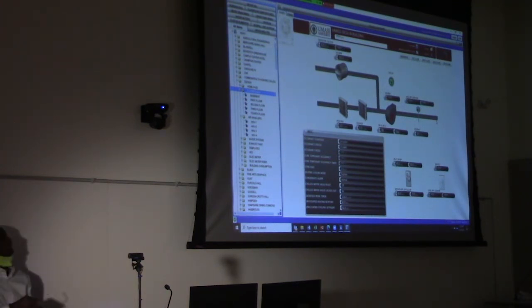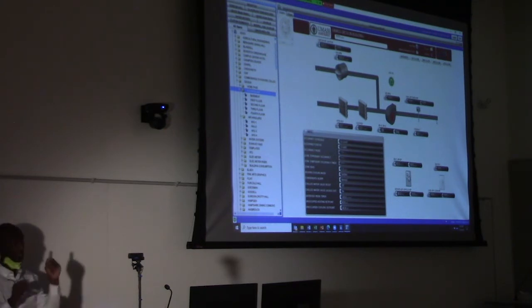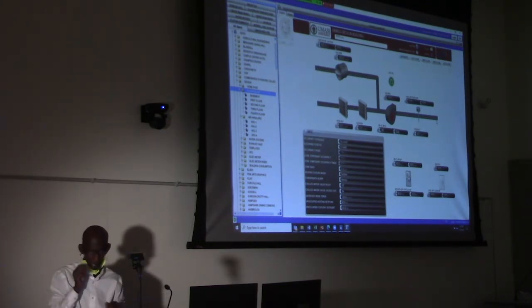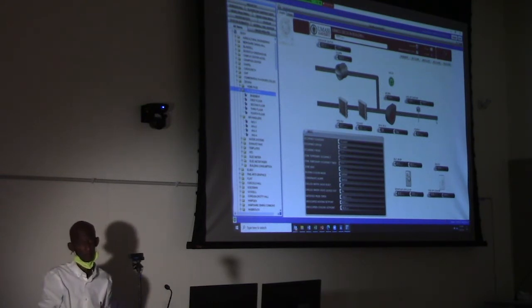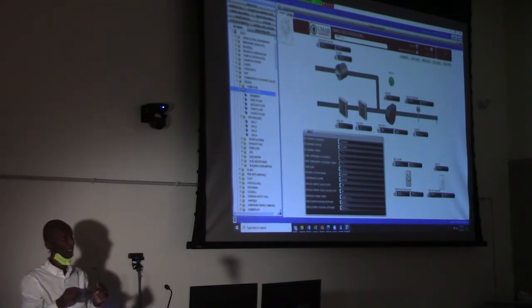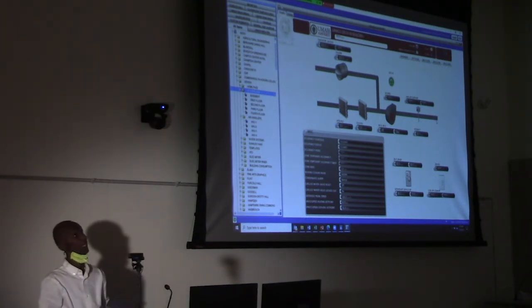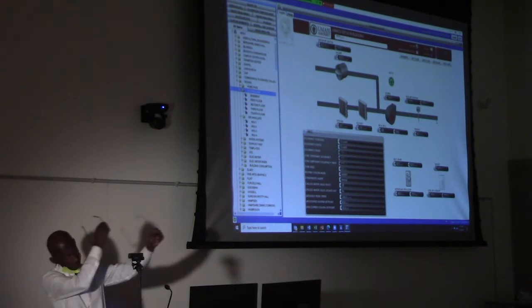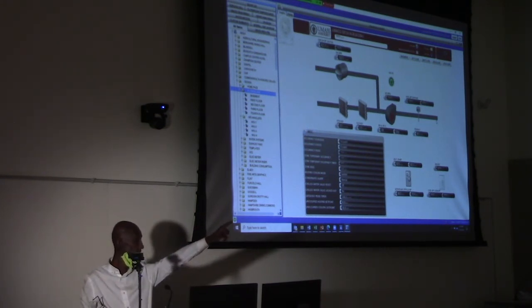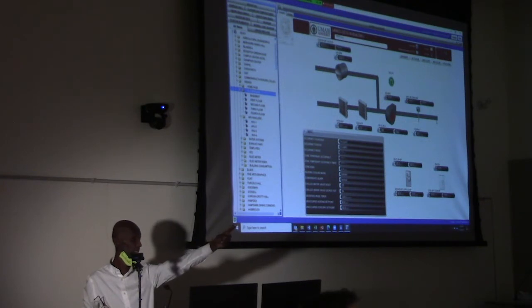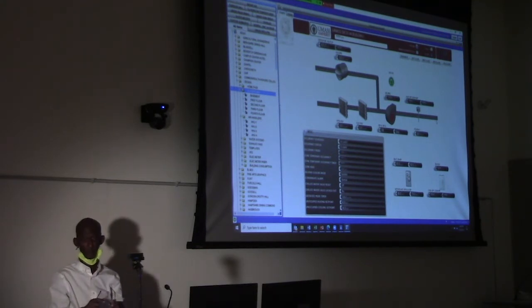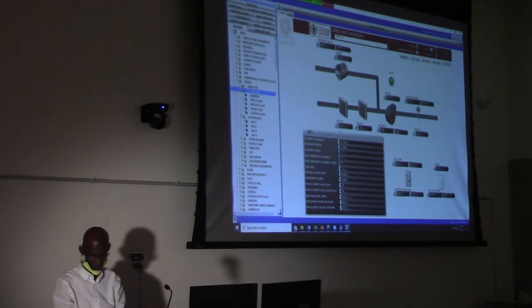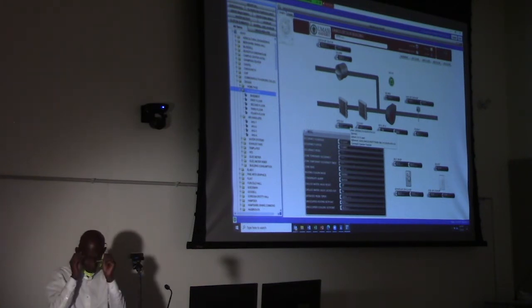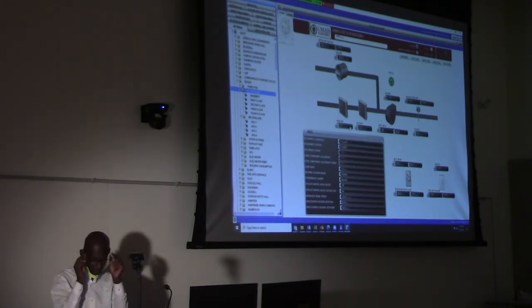I have to try to find it. This may be only supply. I think returns are up above the drop ceiling, in the plenum. Correct. So the coils are hidden. I don't know if you can see over there a silver dot. Usually they are somewhere in the duct wall. And you have a valve here that opens and closes based on the demand and the temperature request in the room.